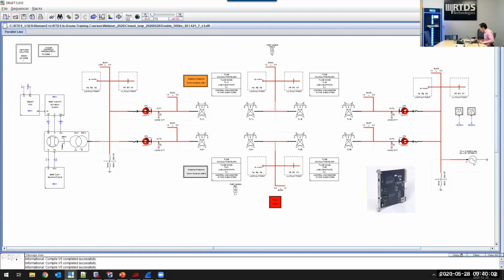Before running the simulation, let's have a quick peek at the hardware used. This is the NovaCor cubicle, and we're using the top chassis here. We have a GTNet chassis as well, which can hold up to 3 GTNet cards or X2 cards, but in this case, we're only using one card for this demo. One module is running Goose. The other module is running the sampled values.